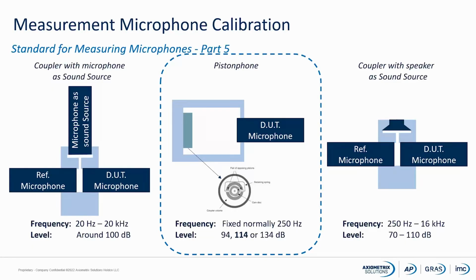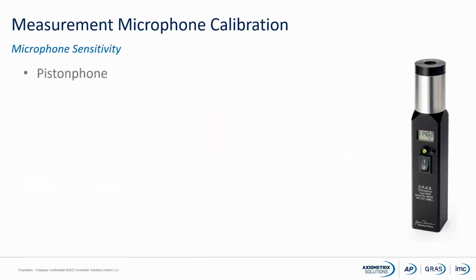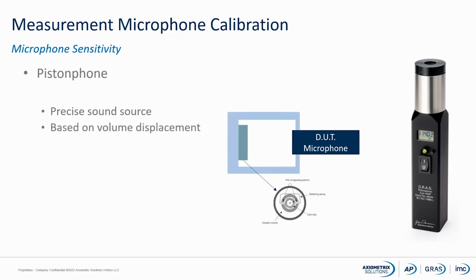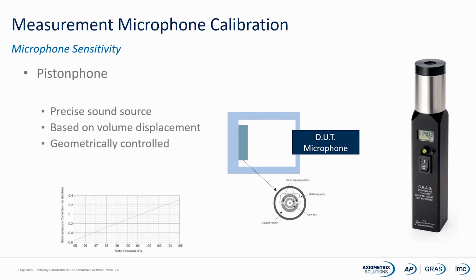We will have a closer look at the piston phone because, as I mentioned, most of the laboratories would actually use a piston phone for the level calibration. The piston phone is a very, very precise sound source. It is based on volume displacement. As we talked about before, we have these two pistons that will build up the pressure inside the chamber. With the piston phone, we have to keep one thing in mind: it has to be geometrically controlled, because we have to compensate for the static pressure.